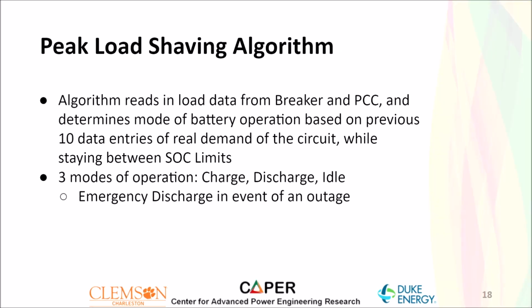Hello everyone, my name is Daniel Sabione, and I'm here to talk to you about our peak load shaving algorithm. So the algorithm starts by reading in the load data from the breaker and the point of common coupling recloser. This was all provided by Duke Energy, and we're mainly looking at the kVA and kW output at these two locations. And we use this to determine what the actual load demand for the feeder is at any given moment, given that this is minute by minute data for the entire past year.